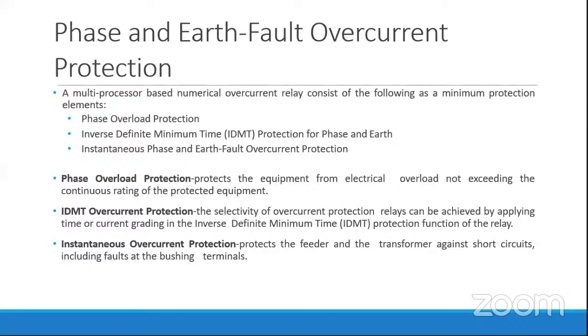Then what is phase overload protection? Phase overload protection protects the equipment from electrical overload, so that it does not exceed the continuous rating of the protected equipment. Generally motors and generators have such overload protections. If a motor is rated at 75 kilowatt, it should have certain characteristics, that it can withstand an overload of up to 80 kilowatt. But if it goes beyond 80 kilowatt, the motor gets damaged. So in order to protect this equipment, we have this phase overload protection.